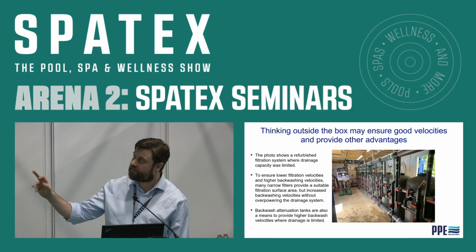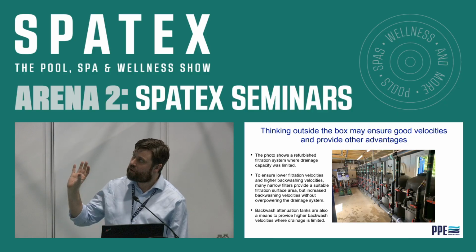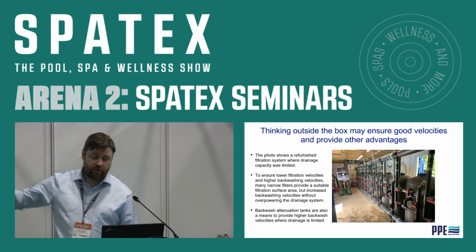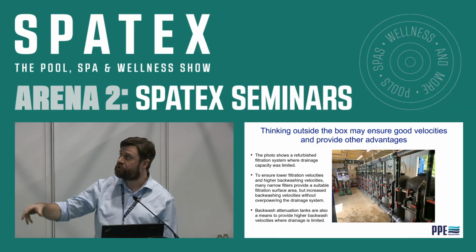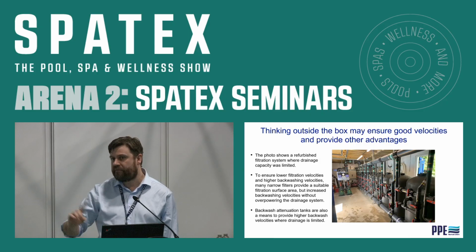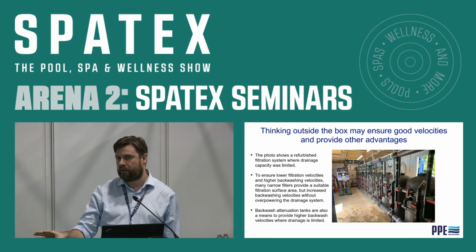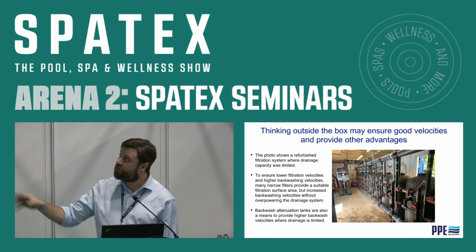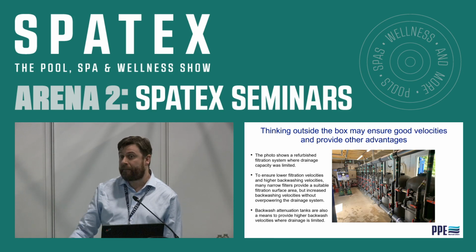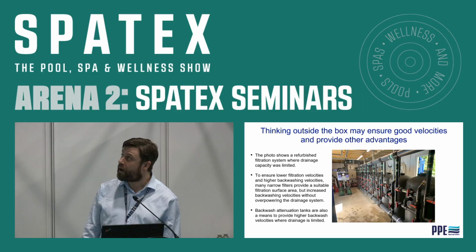One of the great things about this is that on a backwash line, which is coming out from each filter, you put one of those filters onto backwash, and the velocity going through it is going to be much higher naturally, while all the other filters are running on normal filtration mode. And then you're guaranteed a really thorough backwash without turning the pumps on and off. No worries about strainer baskets or anything else.